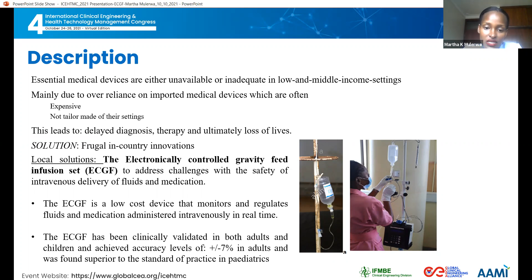Now with the ECGF, all this is automated. All the clinician has to do is connect the giving set through the device. It will monitor the entire therapy session, with alarms that will sound for a slow rate, rapid rate, under infusion, or in case there's occlusion along the IV line. And at the end of the therapy, it will automatically cut off the therapy and sound an alarm to notify the clinician that the therapy is done. Now, the ECGF has been clinically validated in both adults and children. It has achieved accuracy levels of plus or minus 7% in adults and was found superior to the standard of practice in pediatrics.